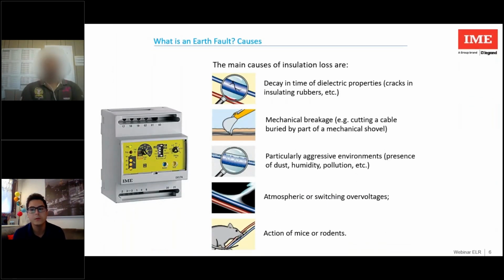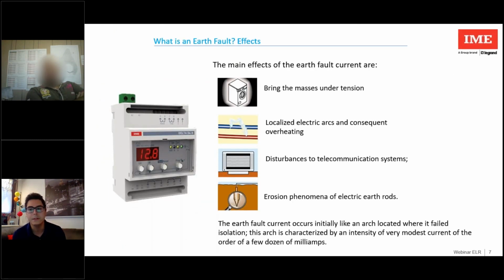Among the main causes of this loss of insulation, we find a decay of the insulation rubbers, mechanical breakdowns due to the accidental cutting of the cables, a particularly aggressive environment with the presence of dust or humidity, or atmospheric events such as lightning, and last but not to be underestimated, the action of mice. Well, what are the effects of these events?